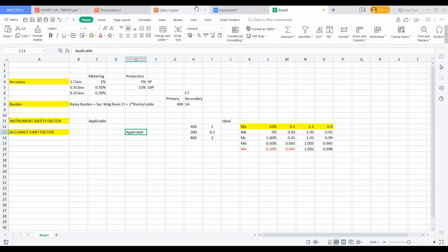When it enters into saturation, there is no flux change when the primary current changes, because the core is already carrying the maximum flux. Since there is no change in flux, there is no secondary current flow. So, in a simple way, in saturation all the current is used as magnetizing current only, and none of the current is flowing on the CT secondary. No flow in the load connected to the CT. Understood, team?